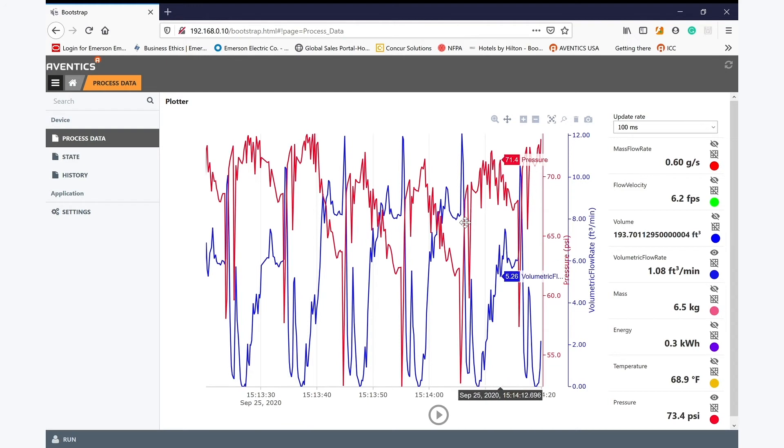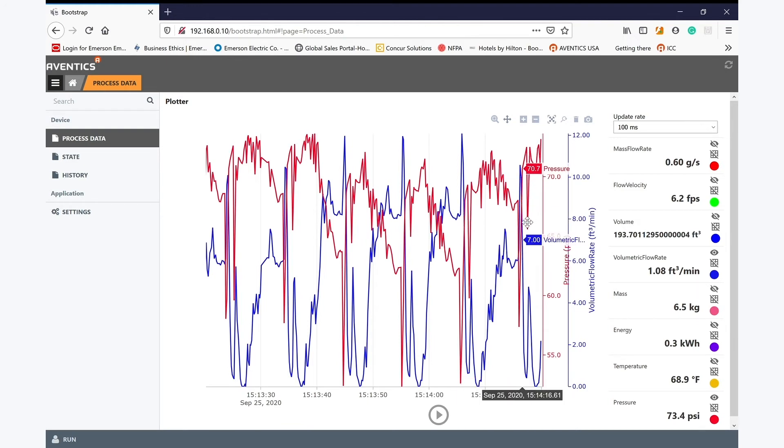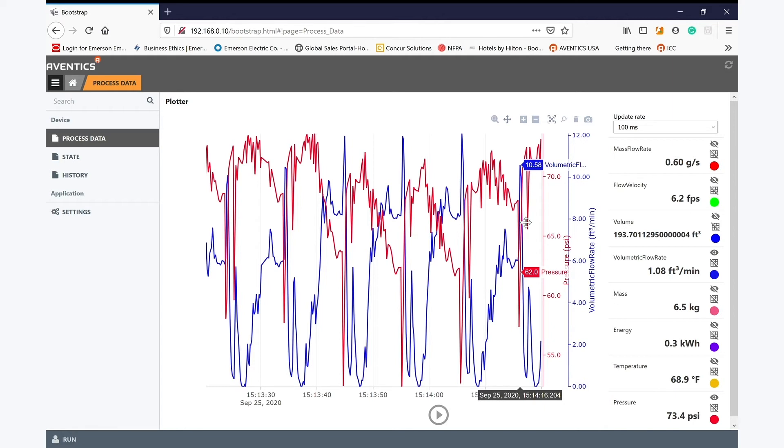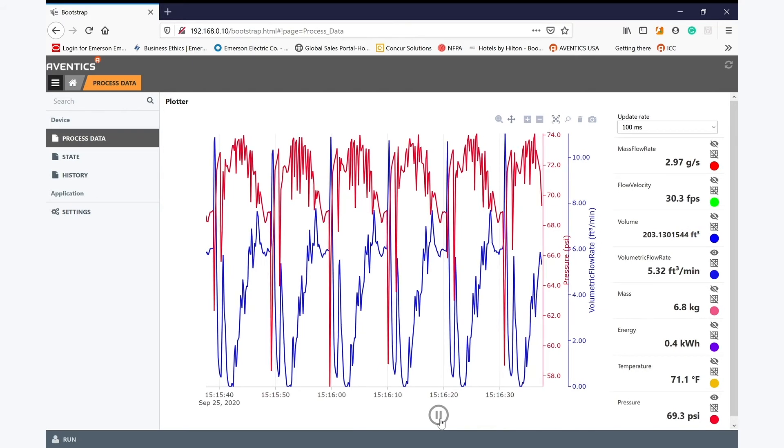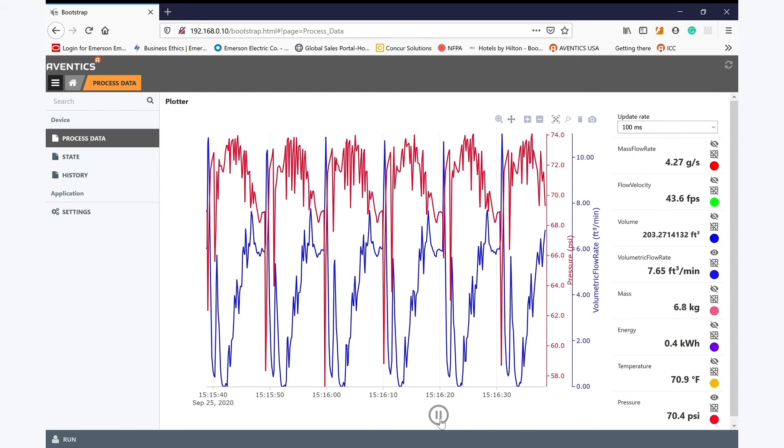This is also captured in the statistical data of the AF2. If we look at the max flow and the pressure, we can see these changing. While the equipment looks like it's operating correctly and completes its operations as normal, very quickly the data provided is giving me insight that something has changed in my pneumatic system.